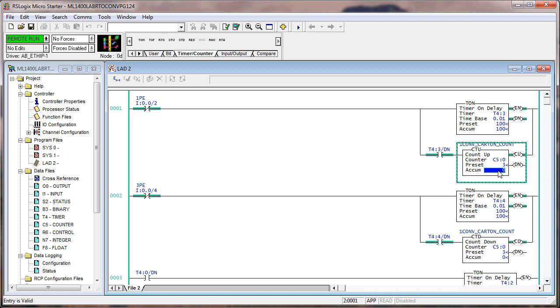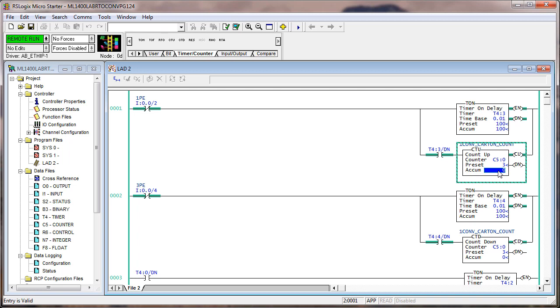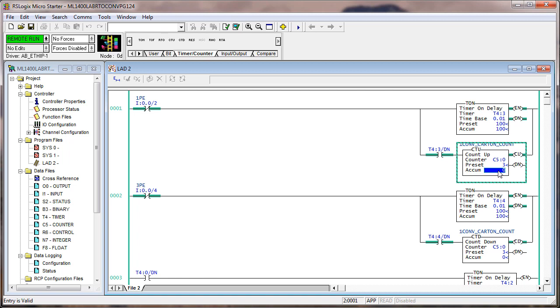Or the carton could be sitting on the stitching where the conveyor belt is joined together. And so it's actually centered out and it's rocking back and forth as it's traveling. In a situation like that, if all that we were doing was using the trailing edge of the photo eye to count up, and it bobbled a couple times, it's clear than it wasn't, then it's clear than it wasn't, it would count all those. You get a miscount. So that timer does a couple things. Not only does it create a little space between them, if you're actually controlling the motors to get how many you want on and off, but the main thing it does, it does prevent counting cartons that are bobbling, counting them more than once. So it kind of filters out noise, if you like that.